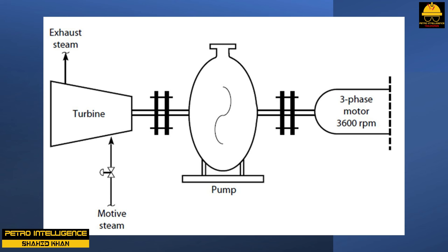How does this affect the amp load on the motor driver? The feet of head has gone down by about 10% and the specific gravity has gone up by about 10%, so the horsepower or work per barrel of liquid pumped remains constant. But the number of barrels has increased by 6,000 barrels per day — about 35% — so the amp load on the motor driver would also increase by 35%. Had I not remembered this prior to cooling the hydrocracker feed, the motor would have tripped off. I had the steam to the turbine increased to decrease the motor amps to 60% of maximum before cooling the gas oil.